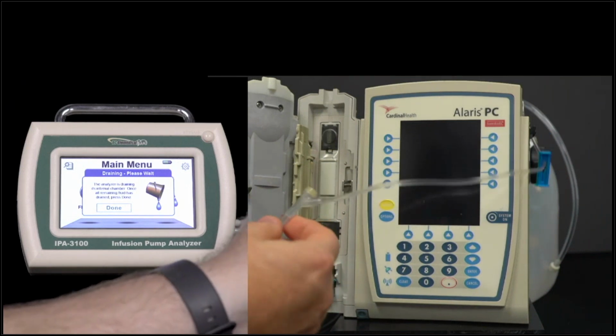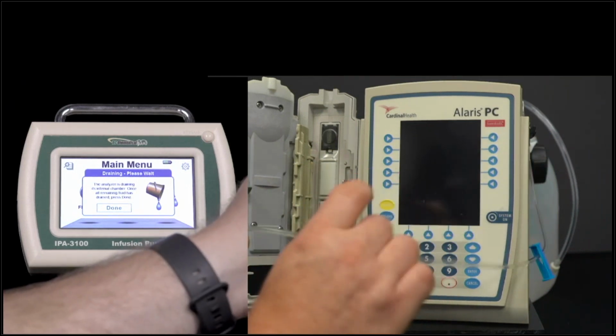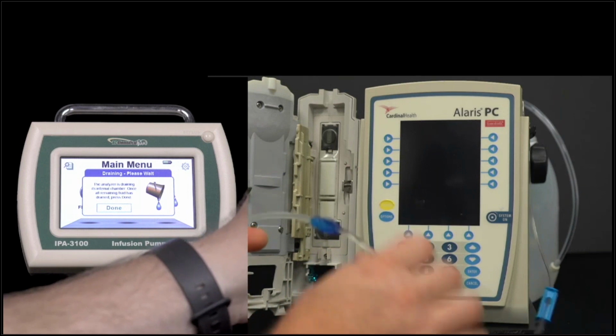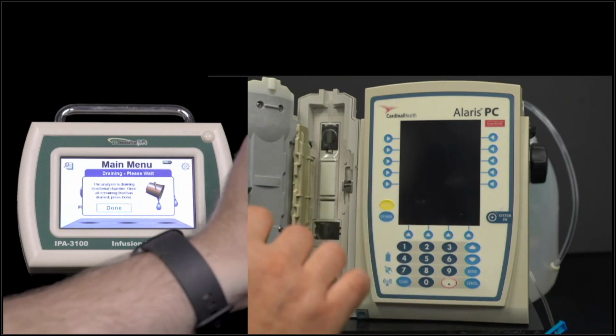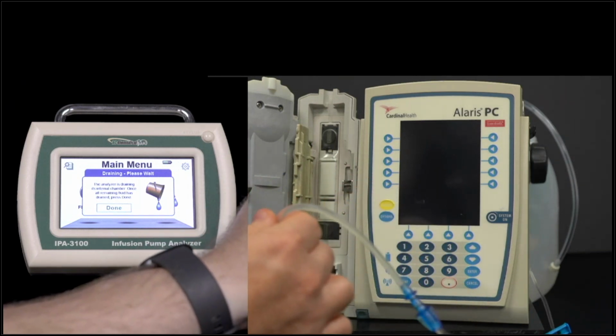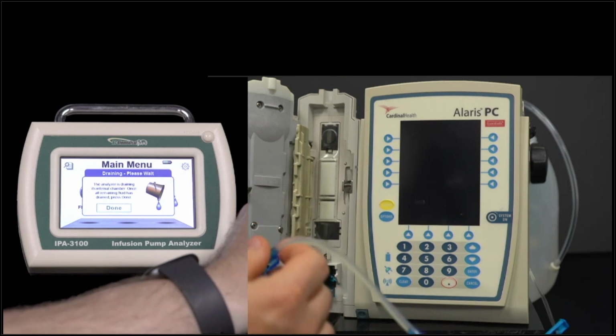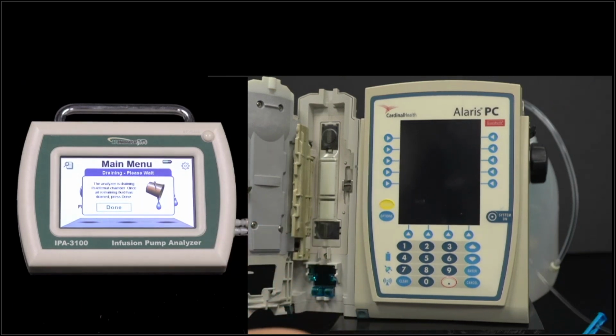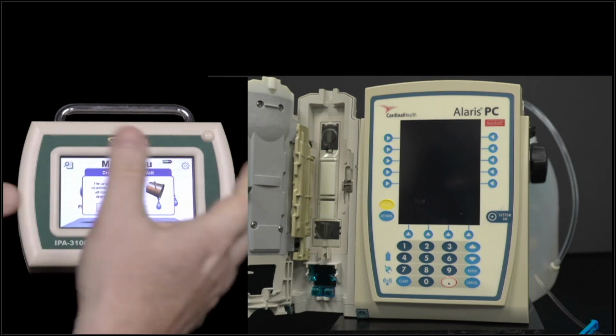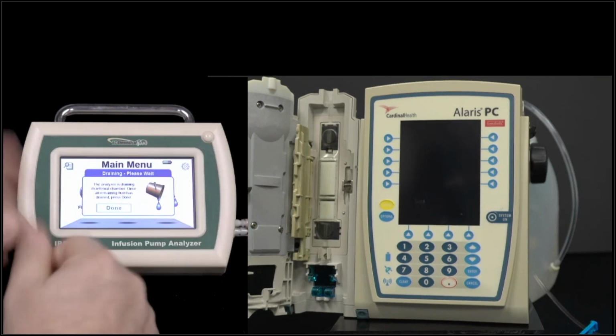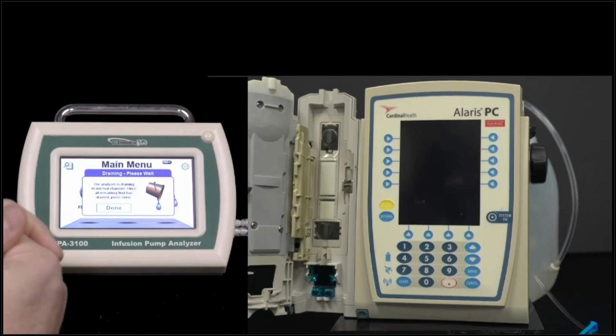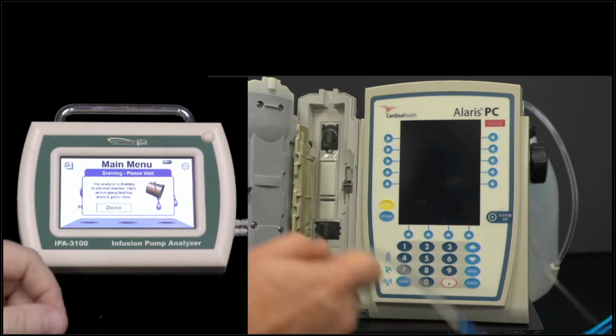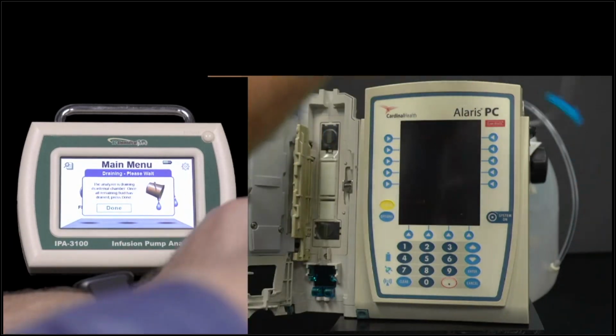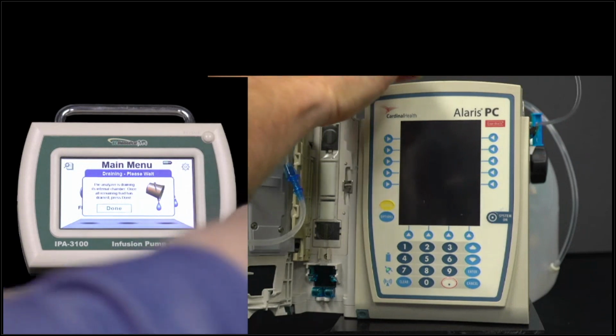Now you may also note that sometimes bubbles like to get trapped in these fittings and anywhere we have connections, so we want to make sure that tubing is clear of bubbles. I mention bubbles not because they affect the IPA-3100 - we could care less about bubbles, we can pump bubbles all day long - but the infusion pump will yell at us if it sees air in the line, as it's supposed to. It's supposed to detect that.